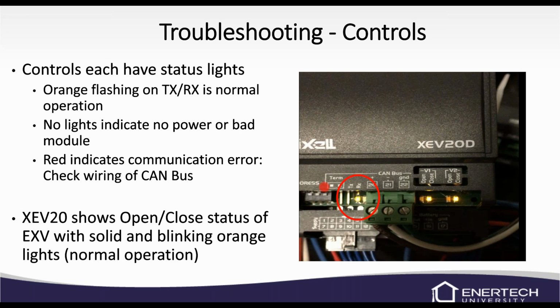There are lights on some of the boards. This is the electronic expansion valve controller here, the XEV. On this controller, you should have a TX and an RX light that would be flashing. They're normally orange. No lights would indicate no power or a bad module, and red would indicate a communication error. We also show an open and closed status over to the right of the valve itself, and it should be solid and blinking orange lights, and that would be pretty normal on there.